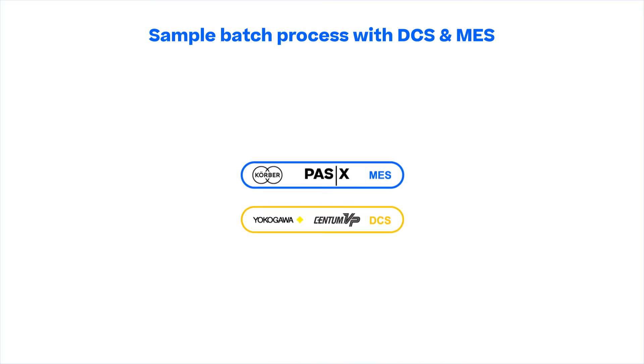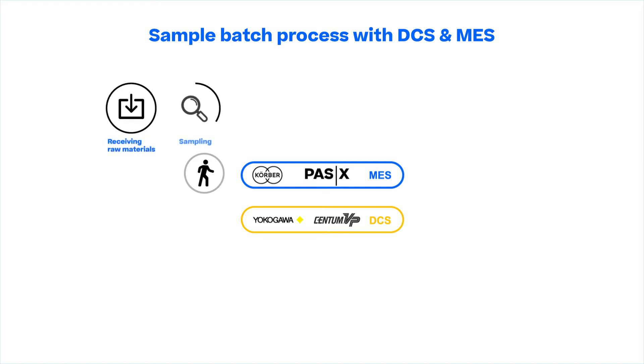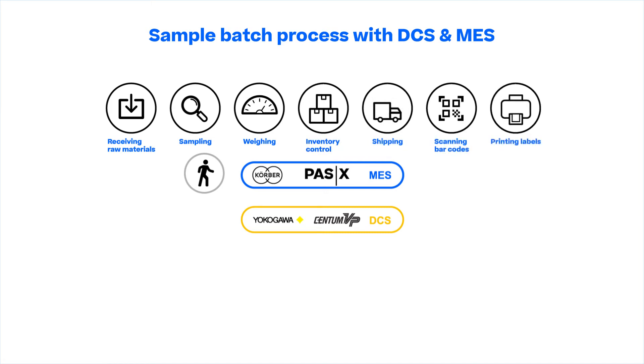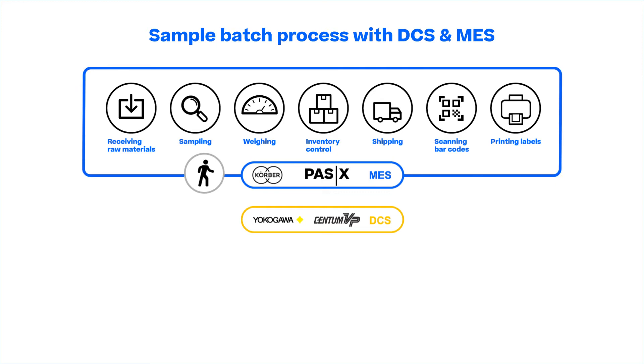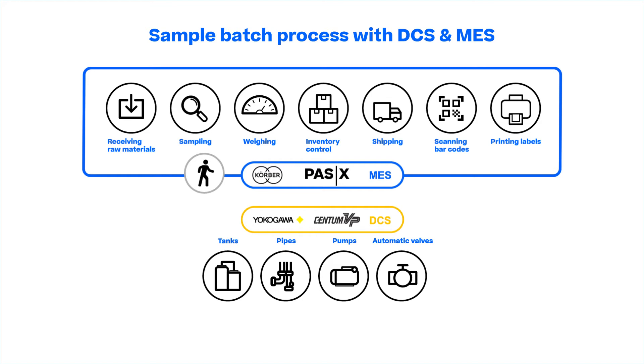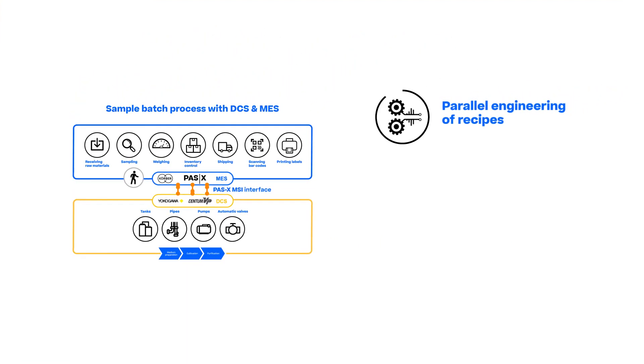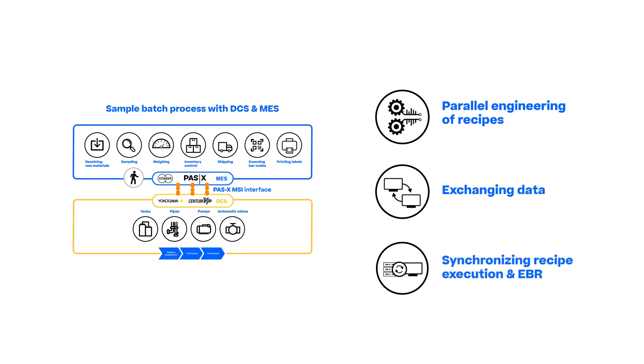The MES guides the operator through all process steps where human interactions are required, such as receiving raw materials, sampling, weighing, inventory control, shipping, scanning barcodes and printing labels. The MES holistically supports the entire manufacturing process, while the DCS controls the sequence of the tanks, pipes, pumps and automatic valves in the medium preparation, cultivation and purification processes. The integration between MES and DCS is achieved by our PAS-X MSI interface, which enables parallel engineering of recipes with a qualified method of exchanging data and synchronizing recipe execution and EBR.